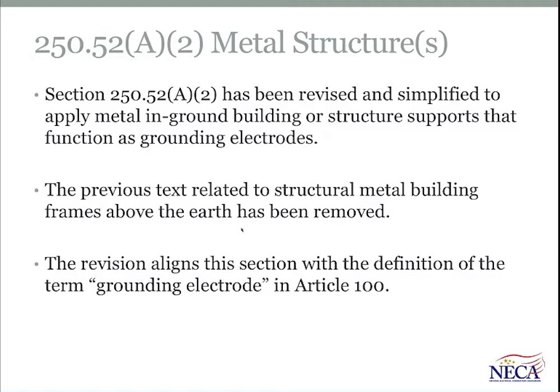250.52 was revised and simplified. We're dealing with structural in-ground supports, whether they're encased or whether they're not encased. The change happened to align this section now with the definition of grounding electrode. The previous text related to structural metal building frames above the earth has been removed. It really hasn't been removed. It was actually relocated to section 250.68C.